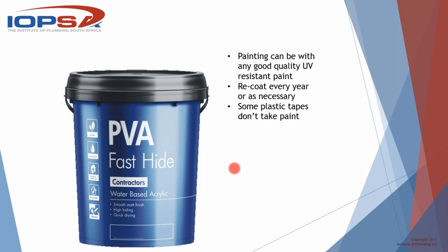Then once you've got a good covering of lagging and a good shell of lagging, now you can paint the lagging in order to protect the lagging from the UV and the ingress of moisture. But it's no use you paint lagging when there's gaps all over the place and you haven't covered the fittings and you haven't mitered properly. Then painting the lagging is not going to do a darn thing. So it's not just about painting the lagging. It's about doing a good job, first of all, and then putting the extra coat of protection on.